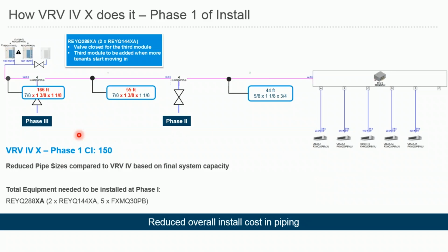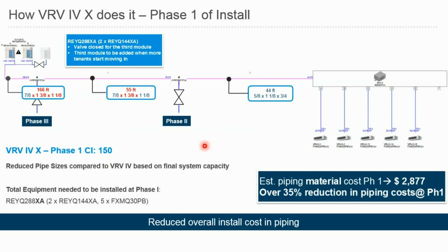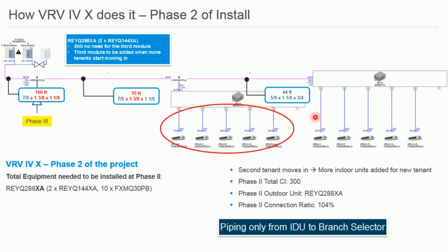And going forward for the next phases of the project, as you can see over here, once the next tenant starts moving into the building, you're still keeping the same main pipe size, 1-3/8" as you see here, instead of 1-5/8". And phase by phase, you're adding new indoor units. In this case, we are at the second phase of the installation. You're still keeping this valve closed for the addition of the third module for the next phase of the project.